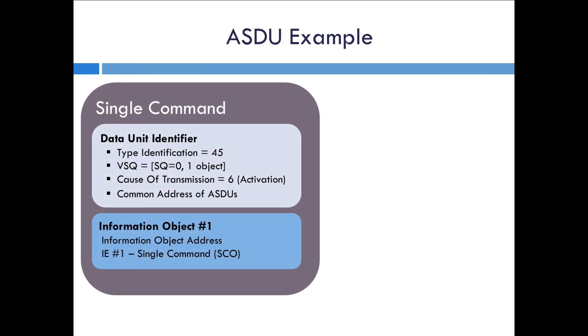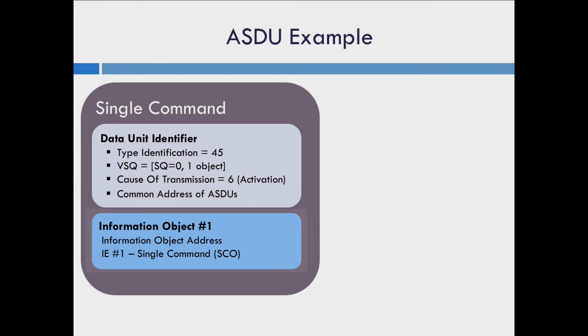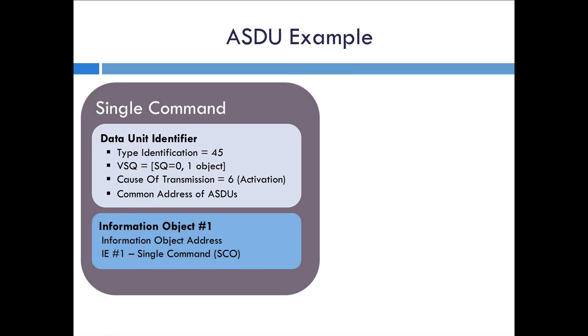When you put together the ASDU for a single command, the information object includes the address for the object being controlled and the SCO, or single command element. In the data unit identifier, the type ID is set to 45 — the number for a single command. The sequence bit is zero because it's not a sequence measurement, and it indicates there is only one object. When starting a command, the cause of transmission is activation, or 6. Then it has the common address for this set of ASDUs.